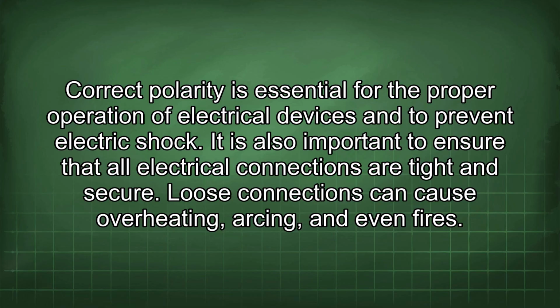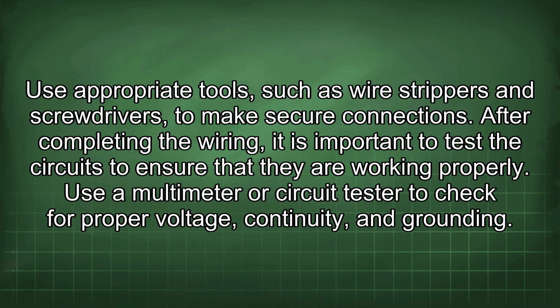It is also important to ensure that all electrical connections are tight and secure. Loose connections can cause overheating, arcing, and even fires. Use appropriate tools, such as wire strippers and screwdrivers, to make secure connections. After completing the wiring, it is important to test the circuits to ensure that they are working properly. Use a multimeter or circuit tester to check for proper voltage, continuity, and grounding.